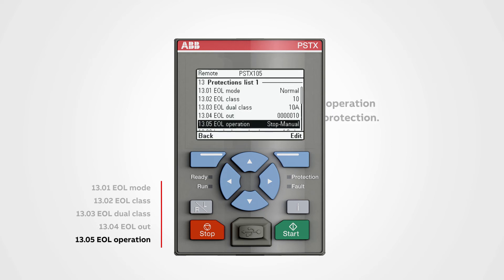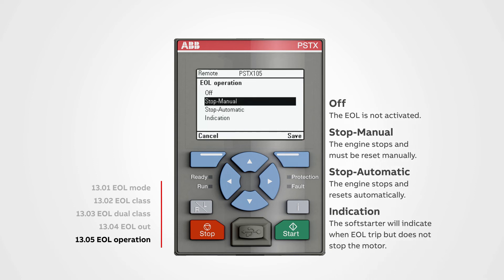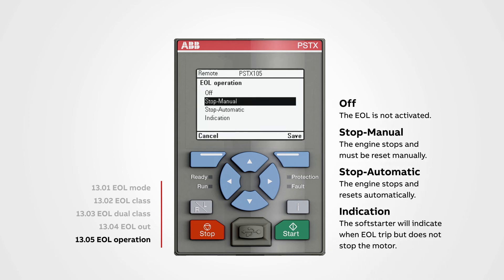EOL operation: set the operation of this protection. Off means EOL is not activated. Stop manual means the motor stops and must be reset manually. Stop automatic means the motor stops and resets automatically. Indication means the soft starter will indicate an EOL trip but does not stop the motor.